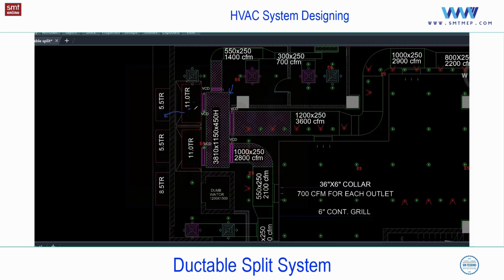In this case, 11 TR, remember, 11 TR means you'll find 2 outdoor units, each of 5.5 TR in Carrier. Similar in Blue Star also. If it is less than 5 or 5.5 TR, you'll find 1 outdoor, 1 indoor. Above that, it depends on the model; you cannot take that as specific. If you talk about Carrier and Blue Star, for higher capacity units you'll find 2 outdoor, 1 indoor. 2 outdoor means 4 pipes connect to 1 indoor. You'll find 2 coils in this. That is technical information we'll discuss at the time of catalog-based machine selection. I'm just giving the idea.